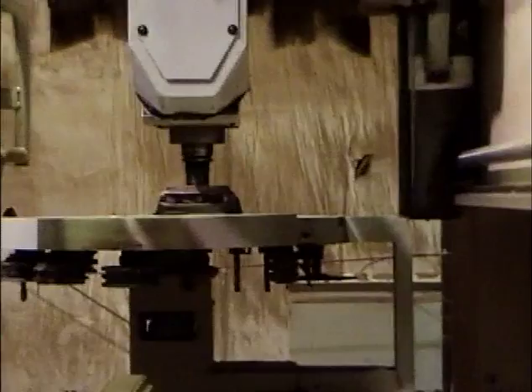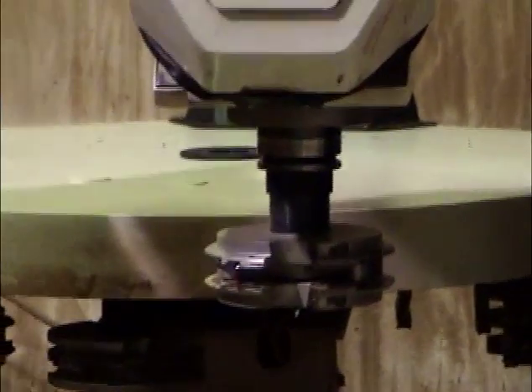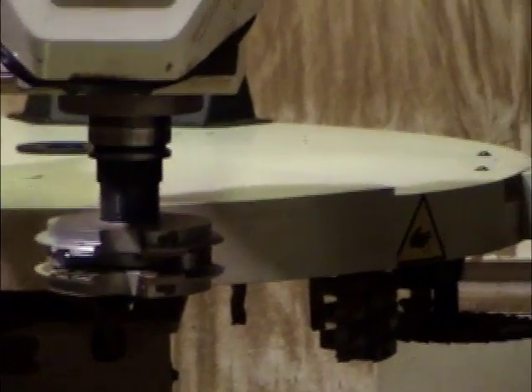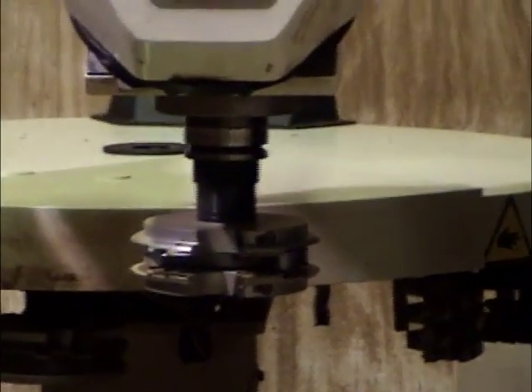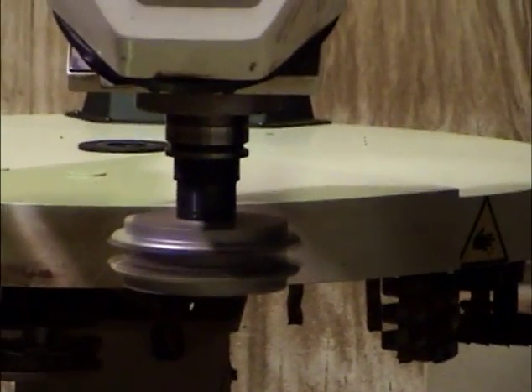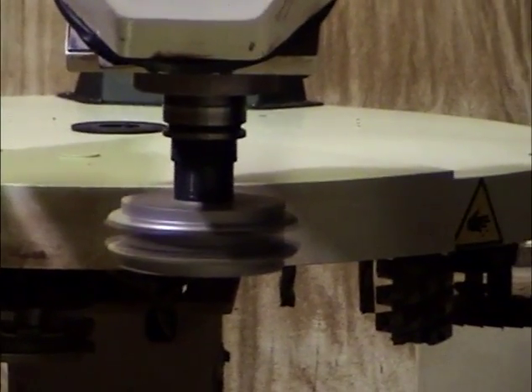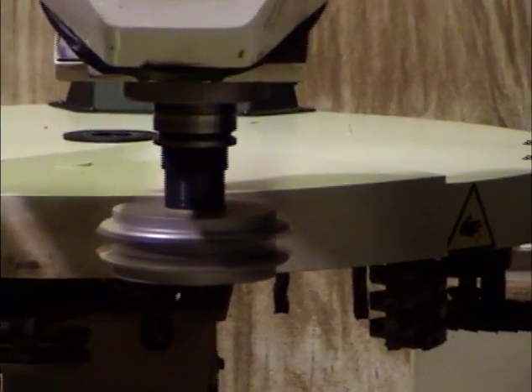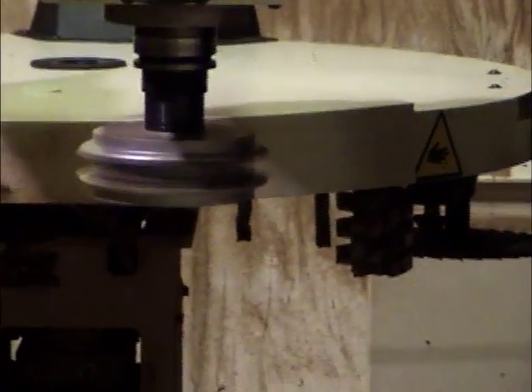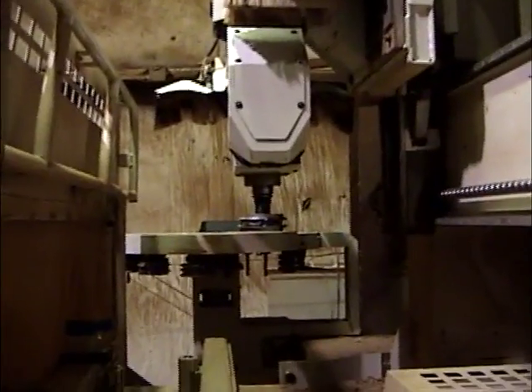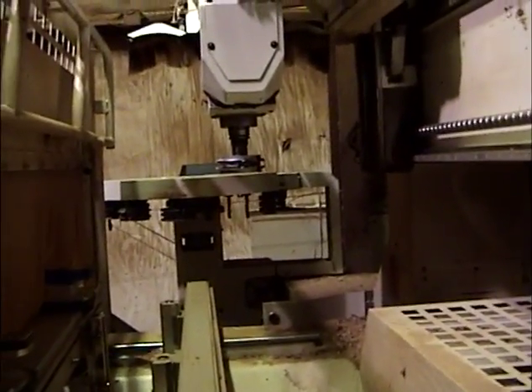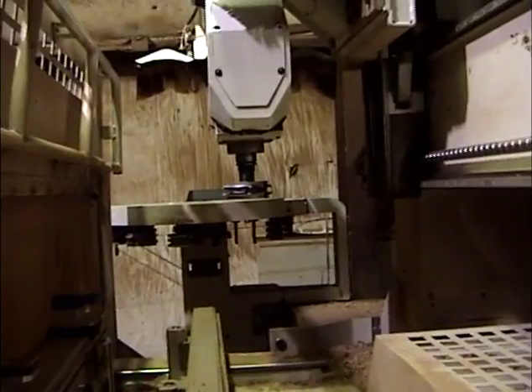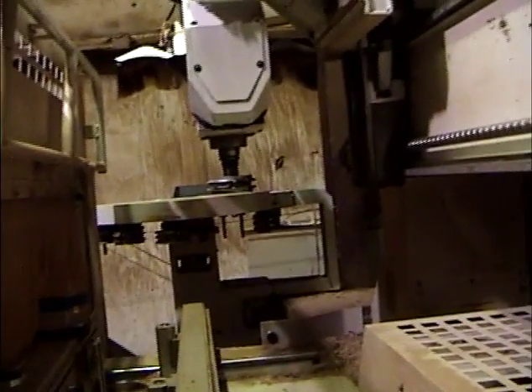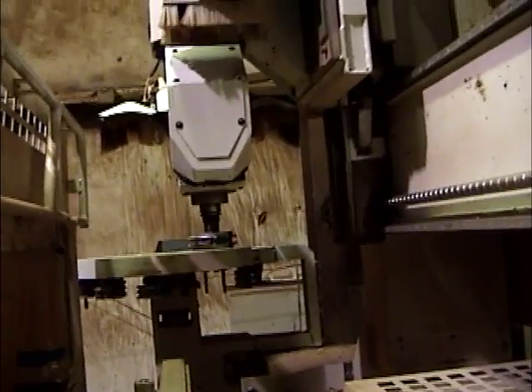Now that I've got a large diameter tool in there, I'm going to go ahead and start the spindle up so that you can see that it works as well. Okay, here we go with the spindle test. This is a large diameter tool, about 4 inches in diameter, maybe 5, running at 8,000 RPM. See, that's very quiet. Okay, so there you have it. You can see that your spindle works, your tool changer works, all the axes move freely, everything works, with the exception of this rail that's been knocked off.